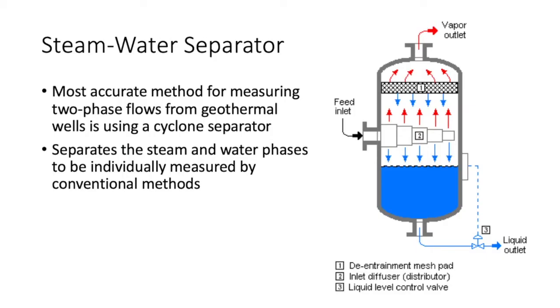A steam-water separator is the most accurate method for measuring two-phase flow systems. It separates the steam and non-condensable gases from the water, allowing each to be individually measured by conventional methods. The efficiency of the system is about 99.9 percent depending on the stability of well flows. A schematic of the steam-water cyclone separator shows how it spins the combined liquid, separating vapor into the vapor outlet and water into the liquid outlet so they can be individually measured.